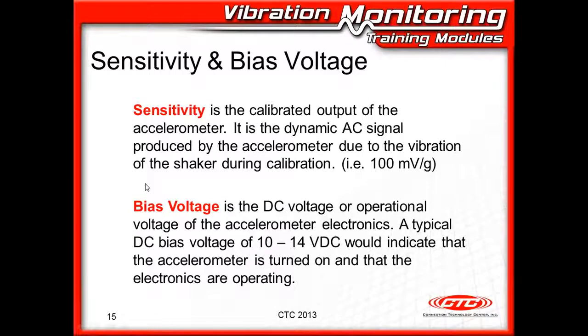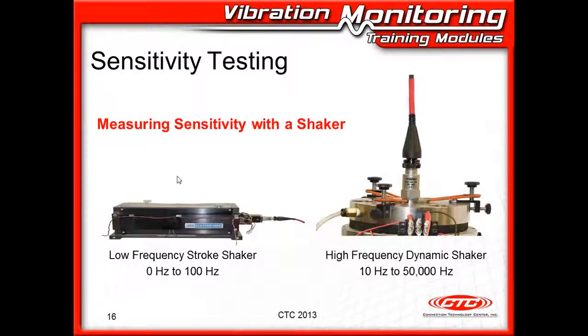The other output is the bias voltage. Now, we don't use this to measure vibration, but we use it to judge the condition or the operational standing of the accelerometer's electronics. So a typical DC bias voltage is 10 to 14 volts DC. That indicates the accelerometer is simply turned on and that the electronics are operating. To test the sensitivity, we need shakers. To test the bias voltage, we simply need a power supply and a meter. So let's take a look at how we would test each of these.